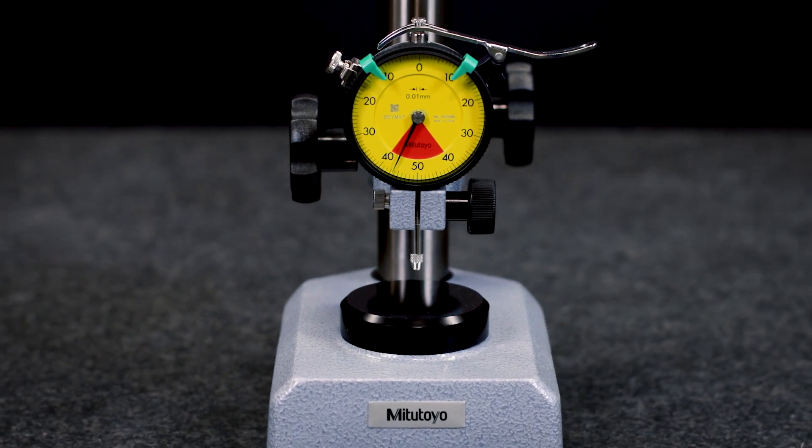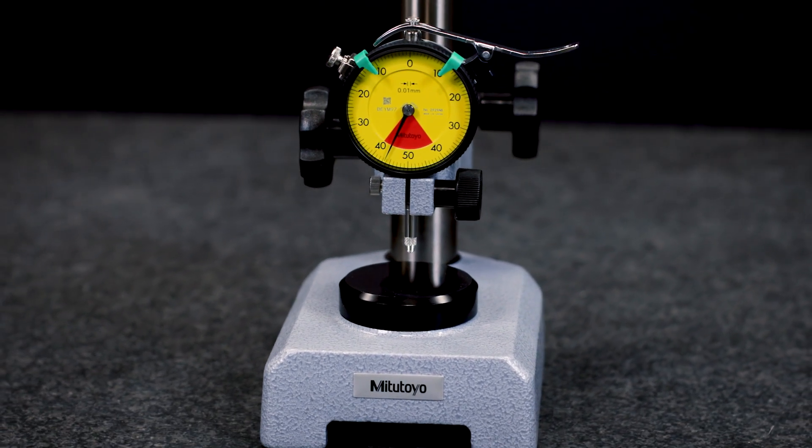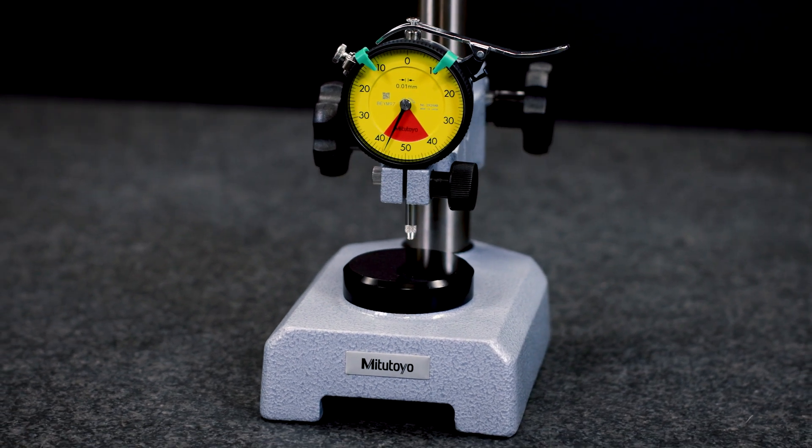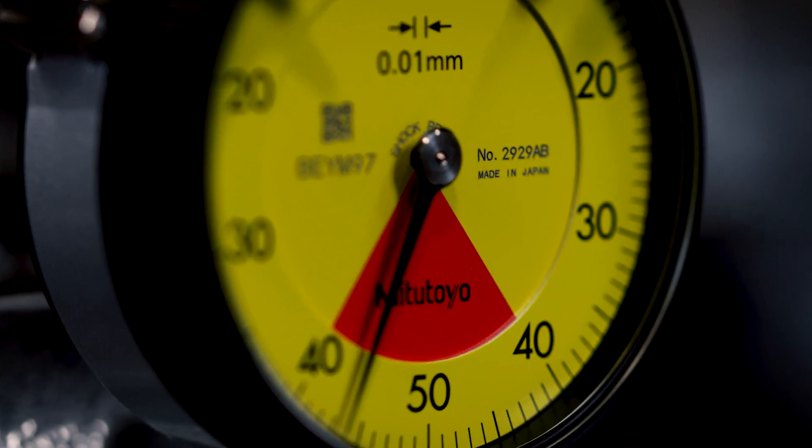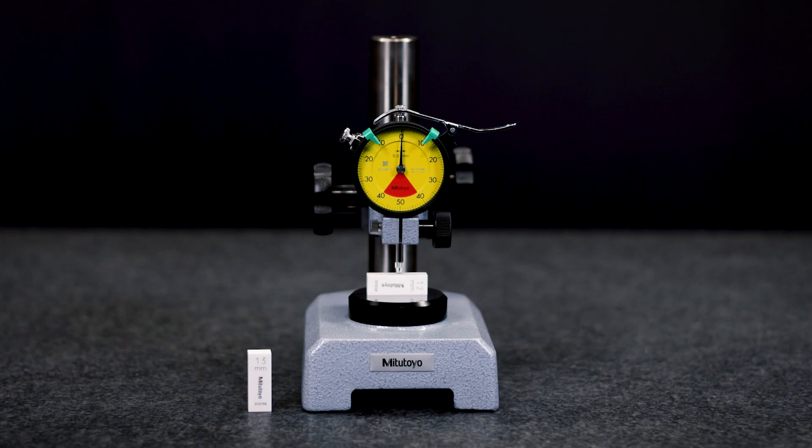To avoid such kind of misreading, one-revolution indicators are a better choice. These are equipped with a dial face with a red out-of-tolerance zone to indicate that the measured part, respectively a measured feature, is clearly out-of-tolerance.